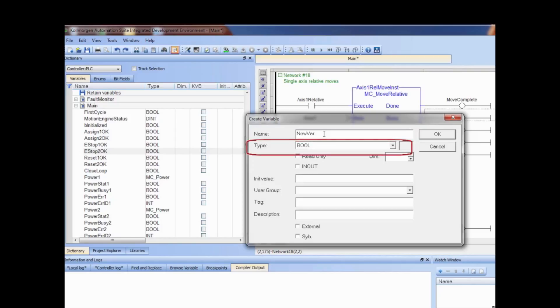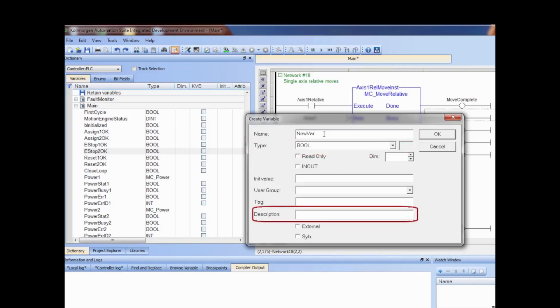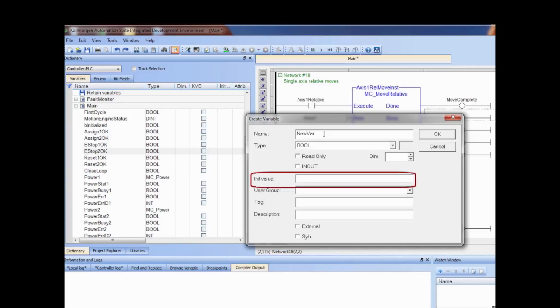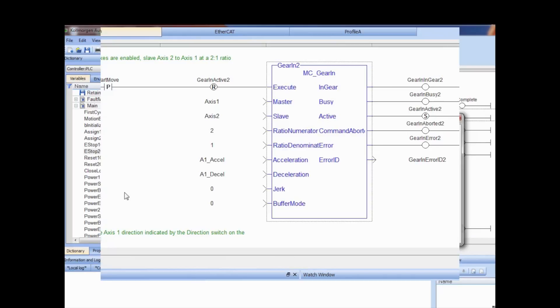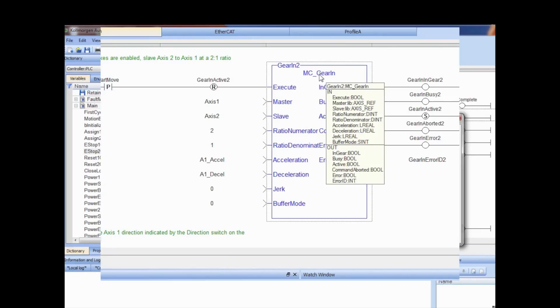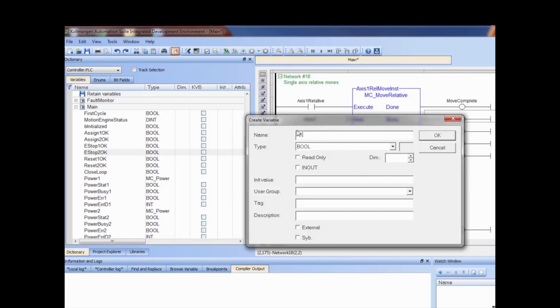A create variable dialog box comes up. Name, type, and description are the same fields as when creating the variable from the program editor. There is also the init value field, used for specifying a starting value for a variable when the project starts up. Note that in the FFLD editor, the needed data types of a function block are displayed when clicking on or moving the mouse over the function block. A1accel and a1decel are dimensioned as lreals because that is the data type the motion function block requires.